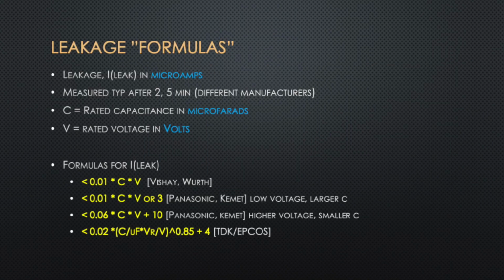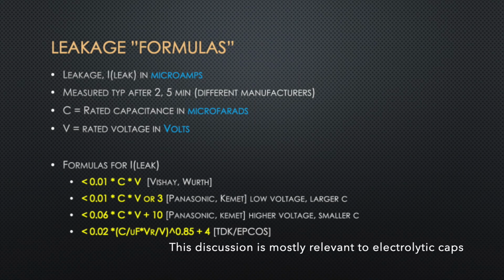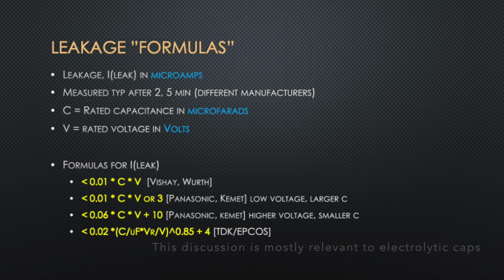So to conclude this video, I'm going to go over the leakage formulas that many manufacturers are using in their data sheets. So the main thing we want to look at is the leakage, that is I leak, and that's usually specified in microamps. Typically the measurement is done after 2 minutes or 5 minutes, or in some cases even 10 minutes, and different manufacturers have different times that they specify. The third, of course, important thing is the capacitance of the device you're trying to measure. It's the rated capacitance in microfarads again. And lastly, we need to know the rated voltage or the maximum rated voltage in volts.